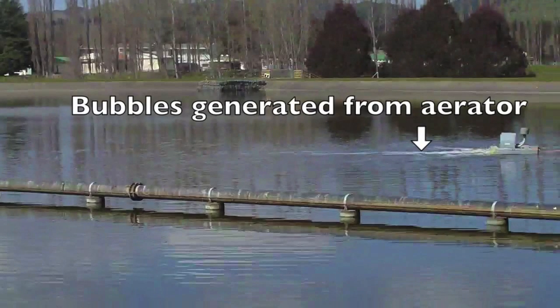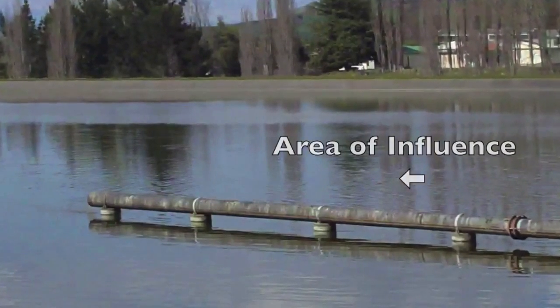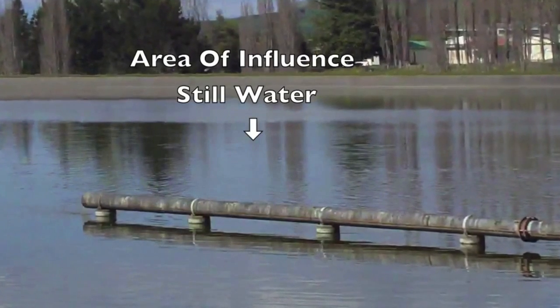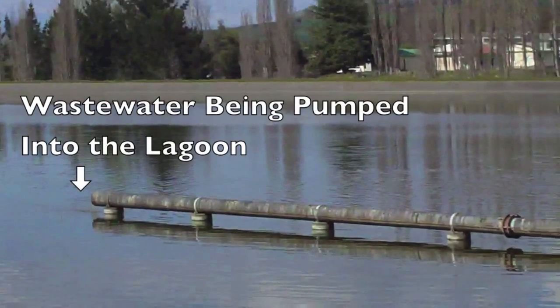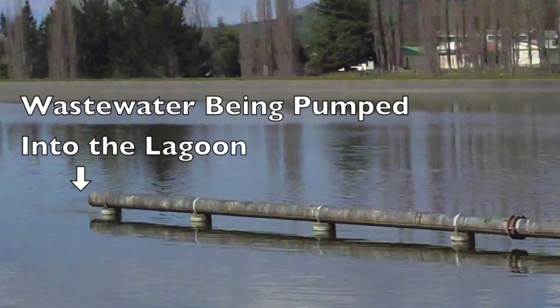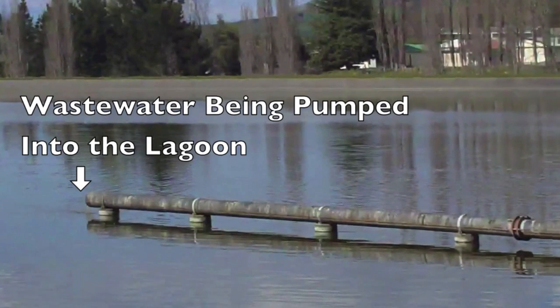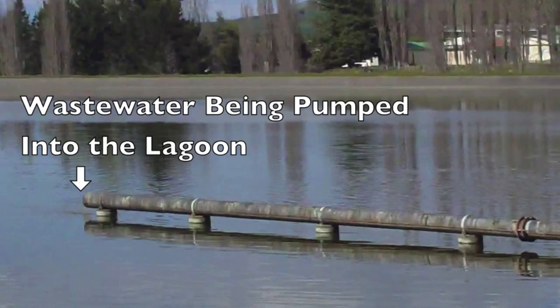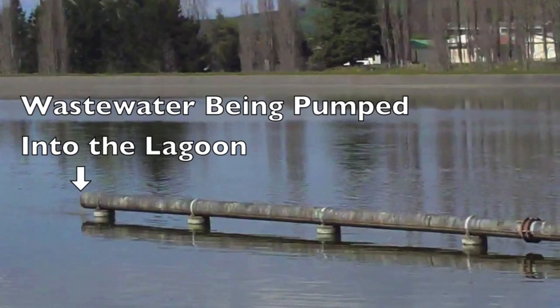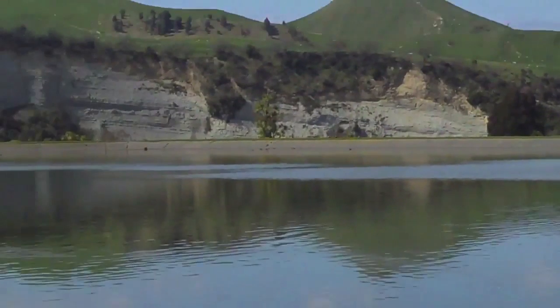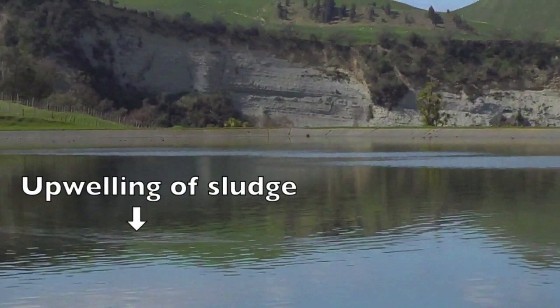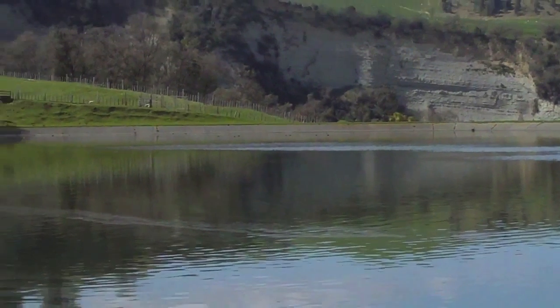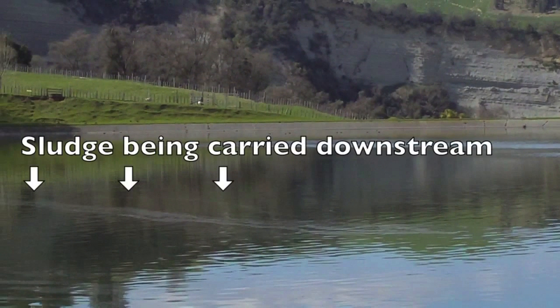There is visual proof of many of these capabilities of the lagoon aerator in this video in the Taihape Wastewater Lagoon in New Zealand. Notice the angle of the aerator to the inlet pipe of the lagoon. Then, notice that the inlet pipe is flowing at the time of the video. Another 20 to 30 meters to the left of the pipe is an upwelling of sludge. This upwelling is the rebound of sludge from the weight of the water entering the lagoon from the inlet pipe. This video proves the 180-degree spread of sludge level water flow of the lagoon aerator.